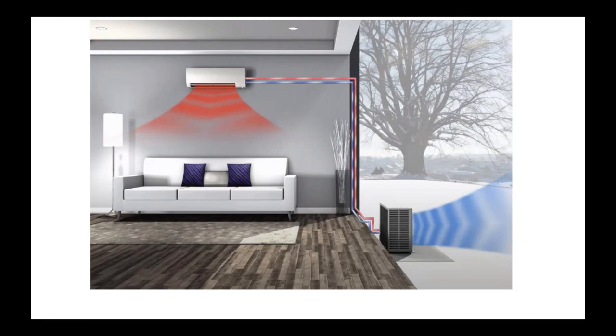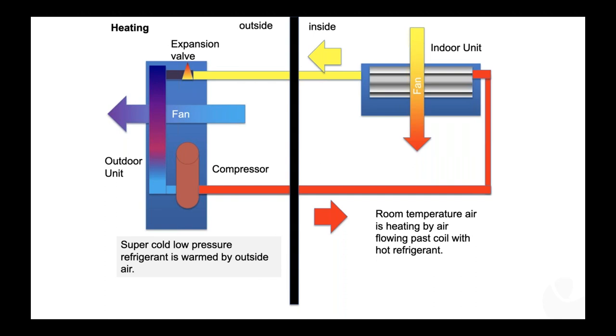Now you'll see that it's wintertime in this scene and it's pouring out this cold air. What's going on? Well, these units can extract heat from outdoor air. So when the air flows through the back of the unit and through the fan and out through the front, it doesn't matter what temperature it is outside, the air coming out of the fan will be colder than outdoor air temperatures because it's extracting heat energy from that air and putting it into the refrigerant line and circulating it to the indoor unit and then blowing out warm air into the house to heat up the sofa and the sheetrock and your cat. Next slide, please.